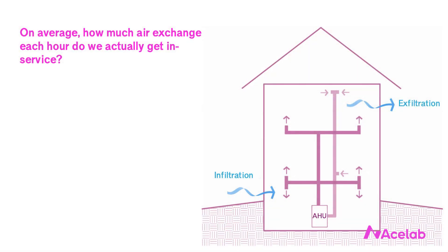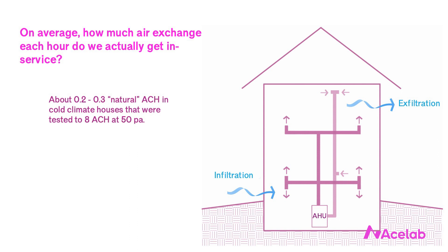Let's use some real numbers to put this in context. The National Research Council of Canada used tracer gas to determine the average in-service air exchange in homes that had been blower door tested to around 8 ACH at 50 pascals — pretty leaky enclosures. They found that on average these houses operated at 0.2 to 0.3 natural air changes per hour, meaning all the air in the house was being replaced about every three to four hours. This is an average — sometimes the air change would be more, sometimes a lot more, and sometimes very little.